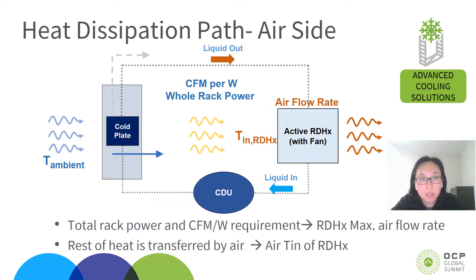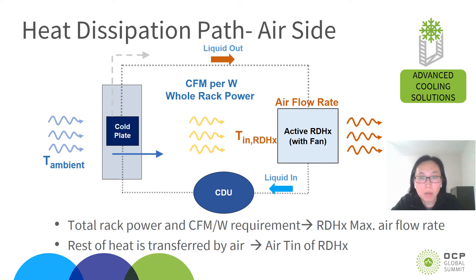At the air side, the cold air from the data center goes through the rack and each of the chassis, carrying some of the heat from the other components cooled by air directly. The preheated air then goes through the rear-door heat exchanger to cool the coolant, becomes even warmer, and is exhausted to the hot air side of the data center. The total CFM going through the rear-door heat exchanger is controlled at the rack level, based on the CFM per watt requirement.